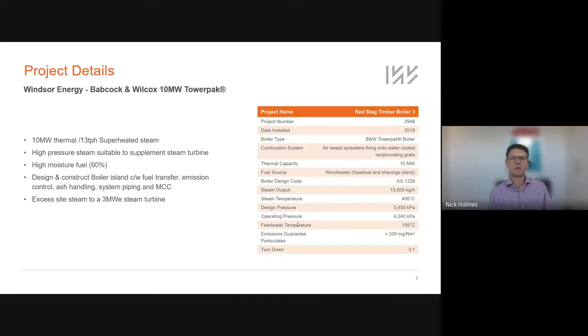The idea with the excess steam was that if we generated the steam at a high pressure, it could then be let down through a steam turbine, which would reduce the steam pressure and generate electricity in the process. Then the lower grade 10 to 12 bar steam would go to the process, to the kilns. The scope of supply was a turnkey, what we call a boiler island: everything to do with the boiler and the associated equipment to drive it, the fuel conveyor system into the boiler, and the piping into the process.